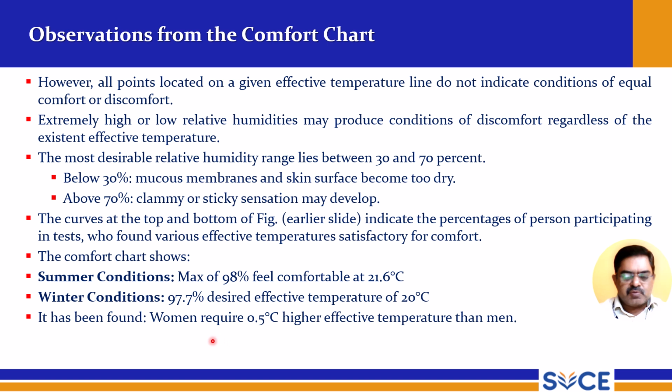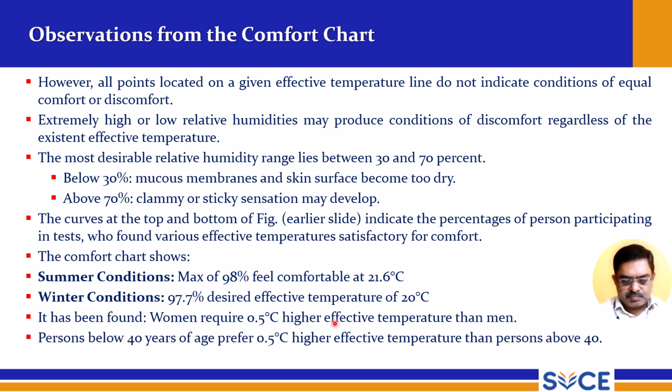It is found that women require 0.5 degrees Celsius higher effective temperature than men. This is found by research only. Persons above 40 years of age prefer 0.5 degrees Celsius higher effective temperature than persons below 40 years of age.